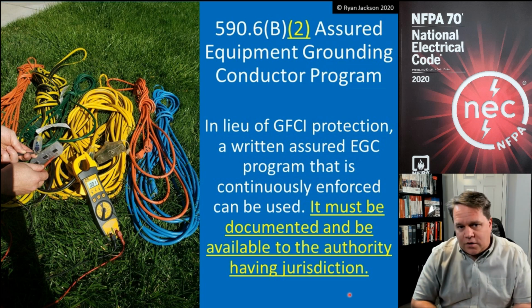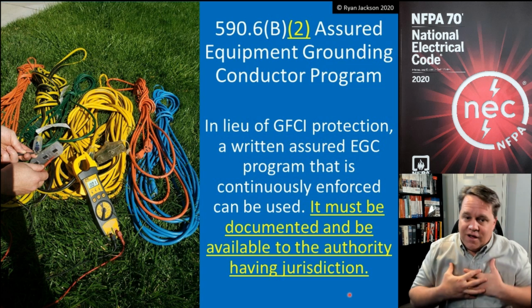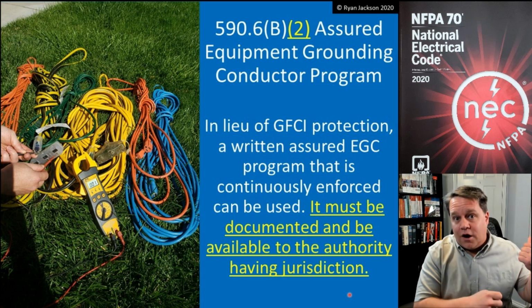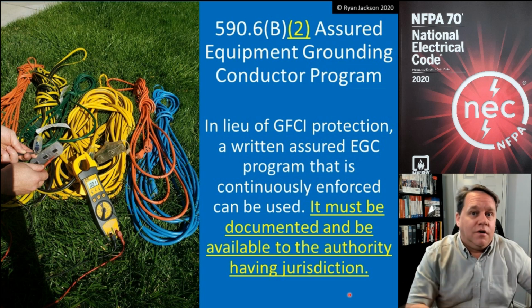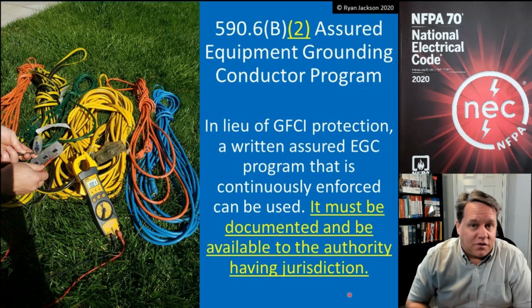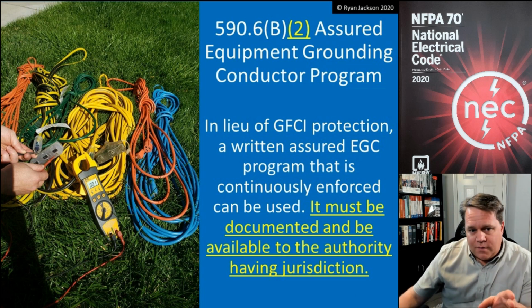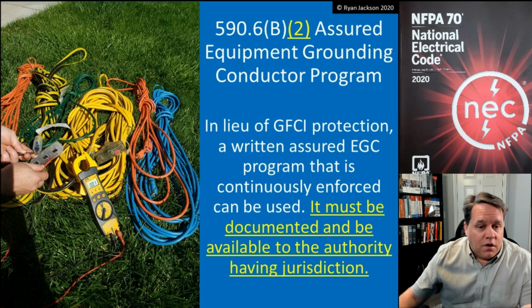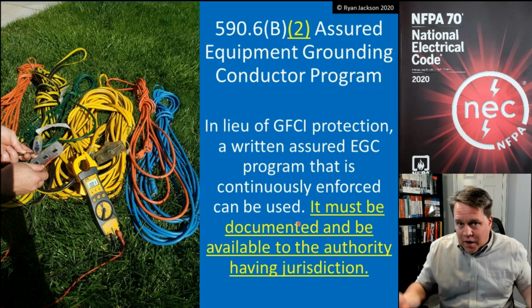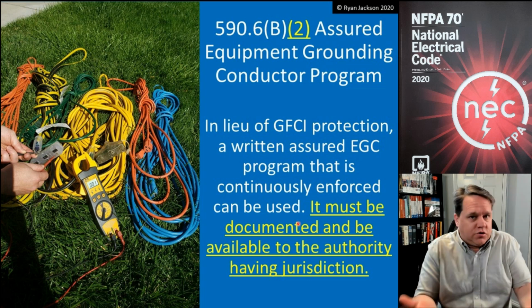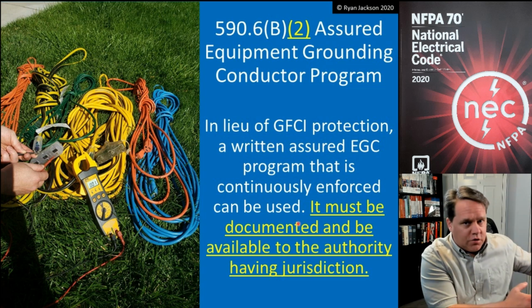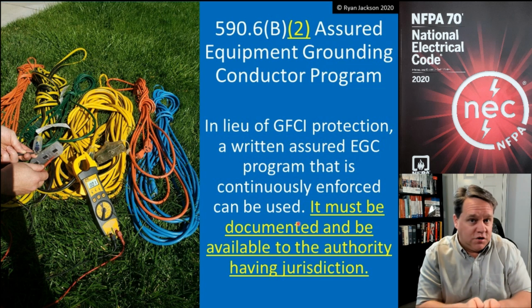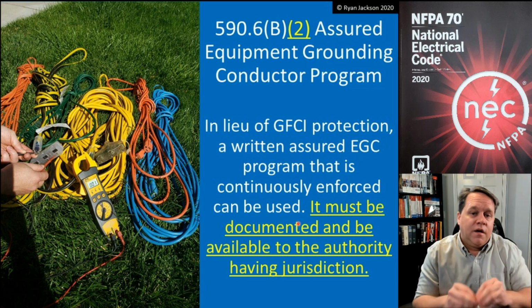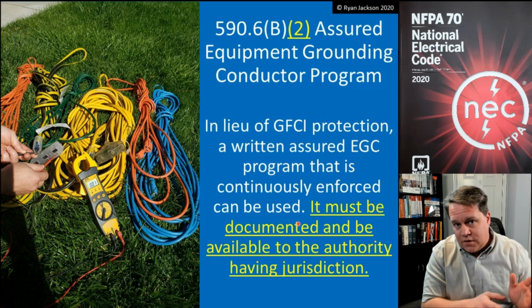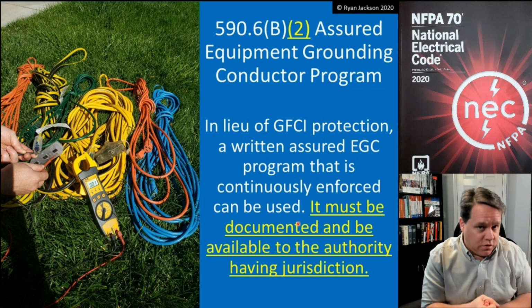So looking at this photograph, and look, I'm just going to be perfectly honest, I just grabbed a couple of cords from my garage, threw them on my grass, and measured continuity a couple of years ago when I took this picture. Let's talk about this for a minute. These are 120 volt, 15, 20 amp cords. So GFCI protection is required for those. The Assured Equipment Grounding Conductor Program is not an alternative for conductors of that voltage and that current. We're only talking about receptacles that are not 125 volt, 15, 20, or 30 amp.